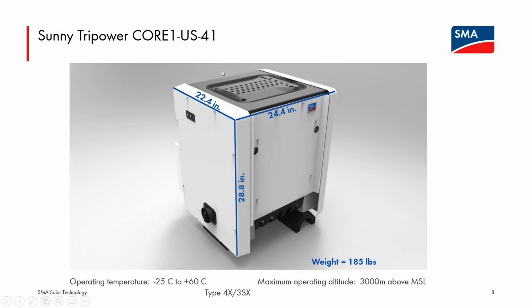Before we show an interesting installation picture, I do want to point out, and I don't know if this is where the inverter's line name came from, but you see the perforations in the top cover of the inverter. The central core of this inverter is actually an airflow chimney. So there are heat sink fins that protrude into that center area, and there is natural convection up through the inverter as a first stage of cooling. And then you may be able to see the fins here, the kind of ribs covering the fan tray that is at the bottom center of the inverter. If the inverter's internal temperature hits a certain level, these fans will come on, and then you're cooling by forced convection. And those fans are speed controlled based on the temperature of the inverter.